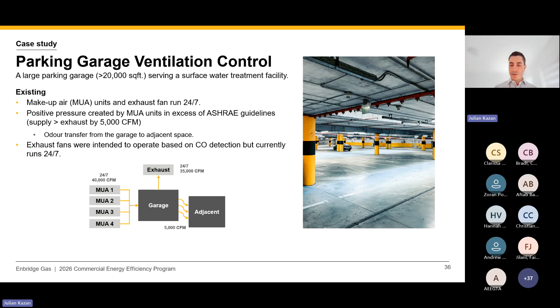And so what are we looking for? What's the data collection? How do we do these calculations, right? First off, we'll just identify units that are serving that space, right? We got 4 MUAs serving those zones. And what are the CFM of those units, right? We don't really want to look at rated CFM. We kind of want to understand exactly, or an estimated amount of CFM that those units are supplying right now as the base case. And then the proposed case is, okay, it's running 24/7 at this 40,000 CFM.